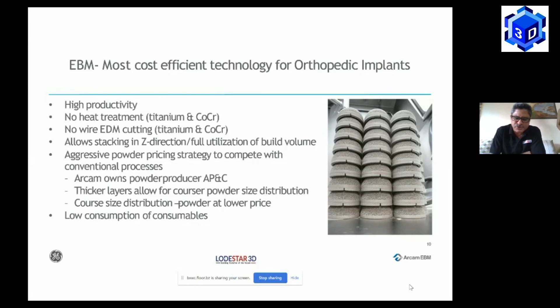So in a way, Arcam owns the powder source, and therefore they provide you consistency on the powder and traceability of the powder, besides the regulatory requirements that you require to qualify the powder from the perspective of the medical ASTM grades qualifications. The other aspect is also the lowering cost impact, because the amount of supports that is needed to be built for a component is lower in the case of electron beam melting in comparison to other powder bed technology, which helps you to also save cost. So this is how electron beam is proving to be a cost efficient and more adaptive technology for orthopedic implant manufacturing. I'll try to explain this in the next slide.